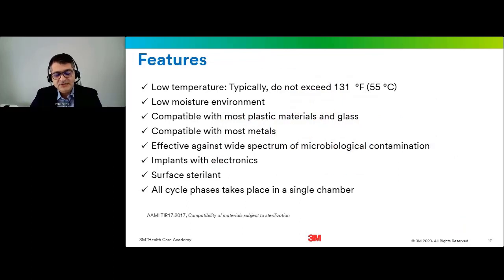Some of the general features of vaporized hydrogen peroxide systems are as follows. They operate at low temperature. By low temperature, we mean they typically do not exceed 131 degrees Fahrenheit or 55 degrees centigrade. They typically do not go over that. They operate in a low moisture environment. If you want to compare with steam, that's saturated steam. Good material compatibility. It means they're compatible with most plastic materials, glass, and metals.